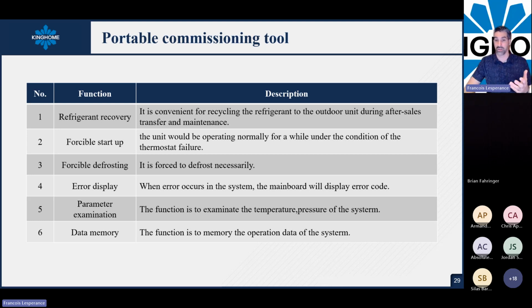Without touching the buttons and all the stuff, directly with the debugger, you can force a refrigerant recovery. You can force a heating start or a cooling start, and you can force a defrost. So you can use this tool to service a unit very quickly. The purpose is to save you time when you are on a job, and you can also save all the data. There's a memory card inside that tool, so you can save the data and send it to a PC or whatever to review it at another time.